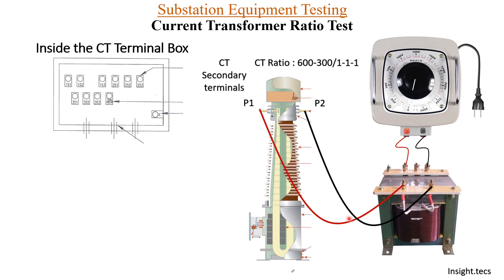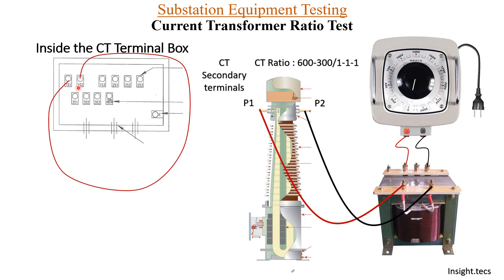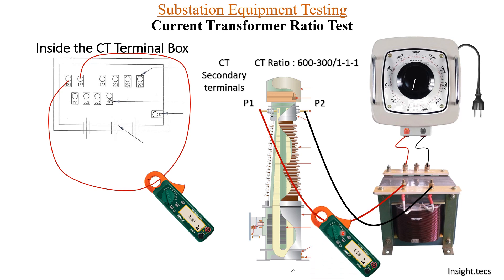The other side of the current transformer output is connected to P2, completing the current path. To measure the secondary current, inside the terminal box we connect 1S1 and 1S2, and measure the amperes on the secondary terminals using a clip-on meter. We also measure amperes on the primary side using another clip-on meter. Once all connections are made, we provide AC supply to the variac.